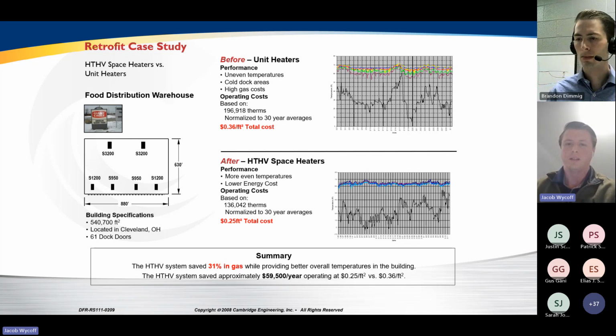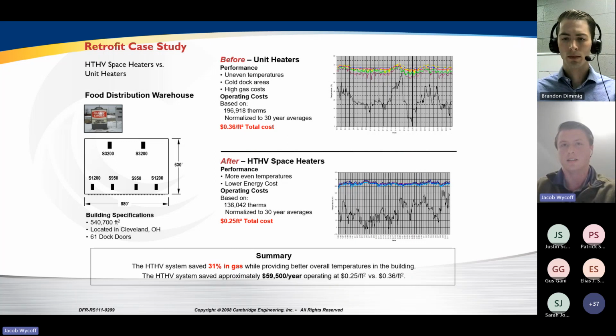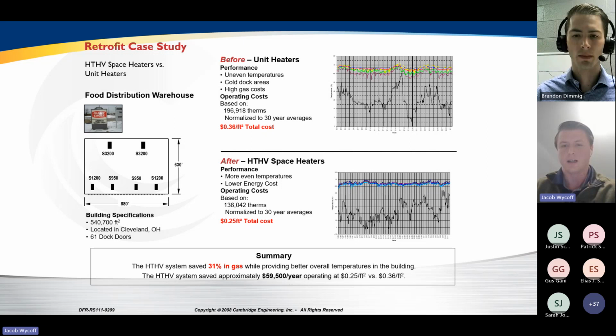So along with being able to get more even temperatures, more comfort for their occupants near the dock doors and having less cold and hot spots, they were able to save 31% in gas, which comes out to $60,000 a year, which can make a huge difference in the profitability of a food distribution warehouse. And ultimately, due to the direct fired efficiency, due to the destratification, they were able to save a large amount of gas while providing better indoor comfort for their occupants.